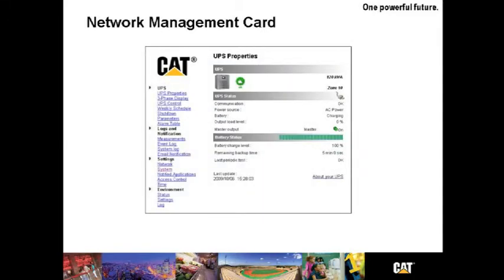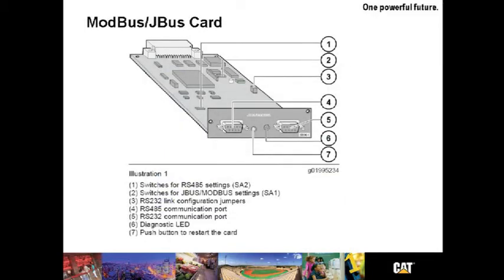The network management card, also standard in the UPS B130, directly connects the UPS to a computer network. It can simultaneously operate as a web server and an SNMP agent. Remote connections are made using an ordinary internet browser or a network management system station. This network management card also provides email and text notifications. The Modbus JBus card, also standard in the UPS B130, provides UPS states and measurements in JBus or Modbus protocols. The JBus hexadecimal or Modbus RTU protocols are used in slave mode. The system provides a communication channel with an RS-485 or RS-232 interface.